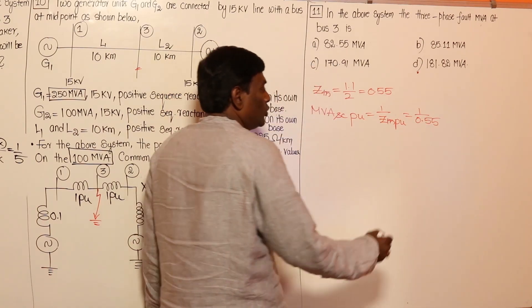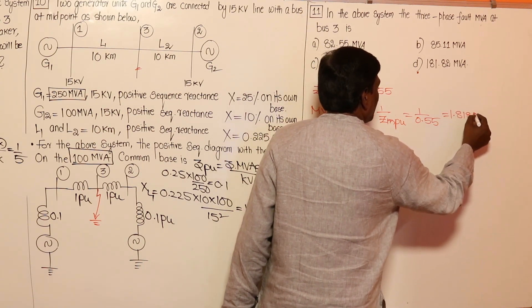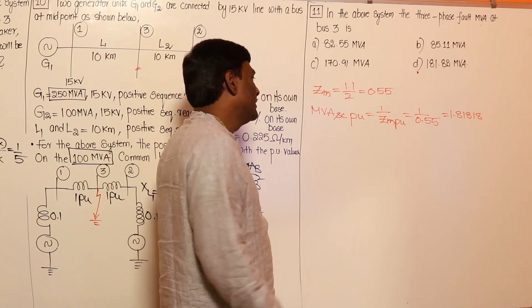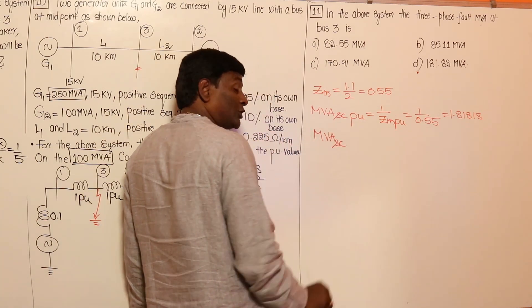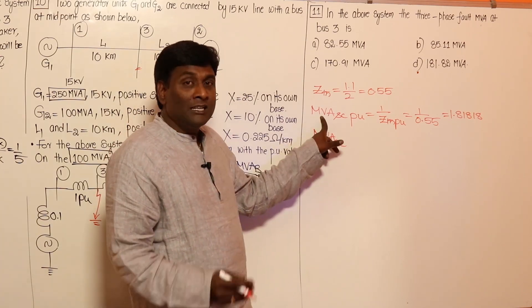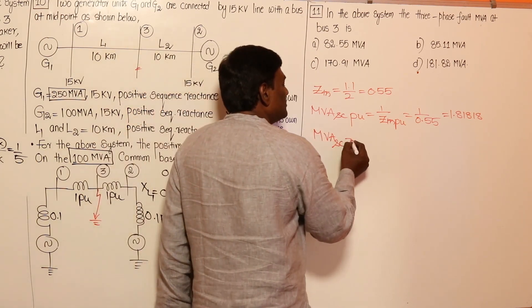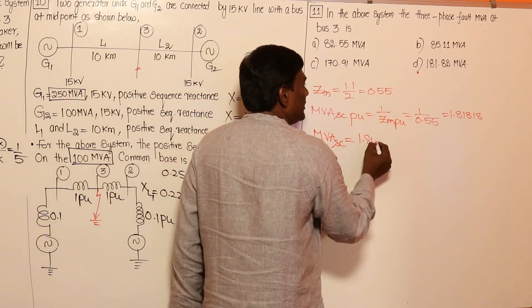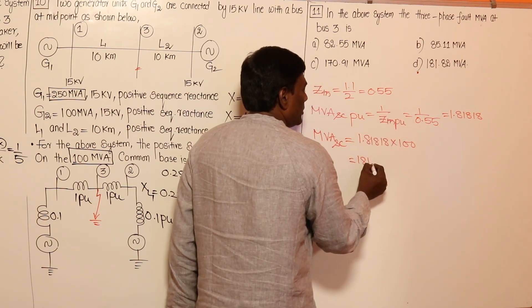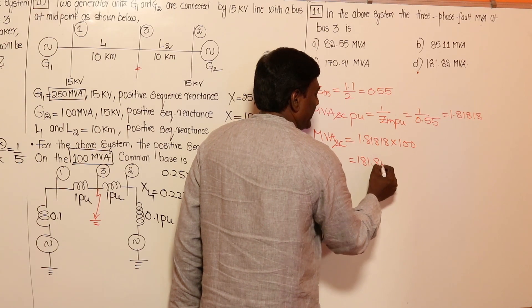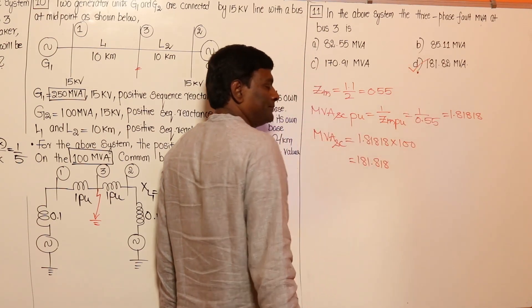So the fault MVA in per unit is 1 / 0.55 = 1.81818 per unit. The actual MVA is per unit multiplied by base MVA: 1.81818 × 100 = 181.82 MVA.